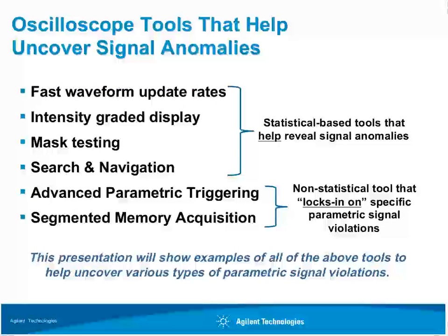Many of today's digital storage oscilloscopes have advanced capabilities that can help uncover signal anomalies. Fast waveform update rates, intensity-graded displays, mask testing, as well as search and navigation, are all tools that can help reveal signal violations — but all these tools are statistical-based. For instance, with a waveform update rate of up to 1 million waveforms per second, Agilent's 3000X series scope can catch events that other scopes miss. But what if an anomalous event occurs just every billion trigger events? Then we need advanced parametric triggering, a non-statistical oscilloscope tool that can lock onto parametric signal violations. If you can specify a trigger condition that uniquely describes the signal characteristics, the scope's hardware effectively goes into babysit mode and waits for that event to occur.